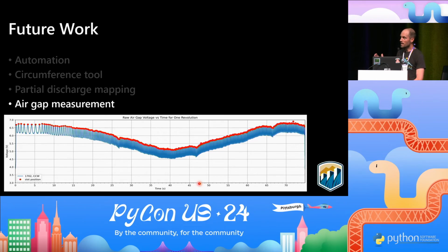And that's taking a proximity probe, slapping it on the rotor pole face. What a proximity probe does is measure the voltage for grounded iron. So it sees iron, copper, iron, copper. And the signal makes it look like it's close, far, close, far.